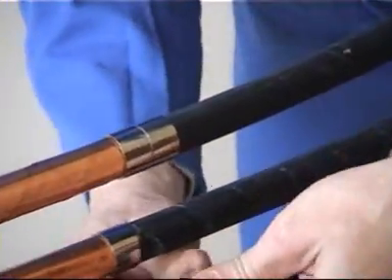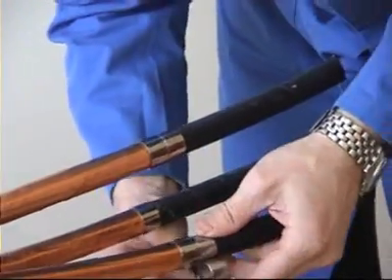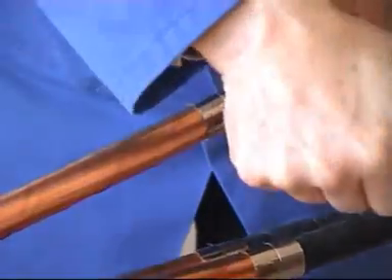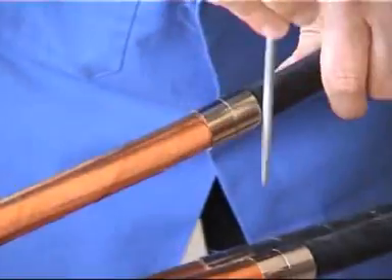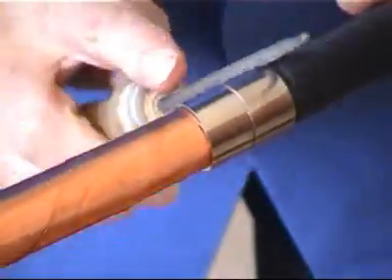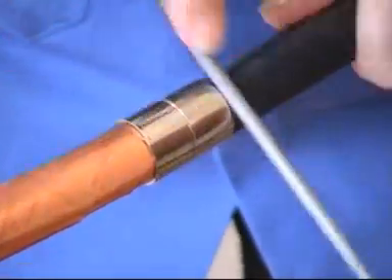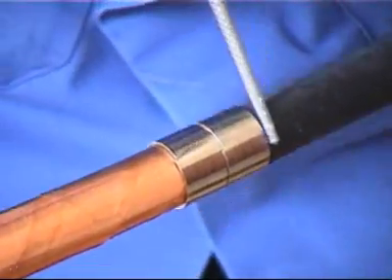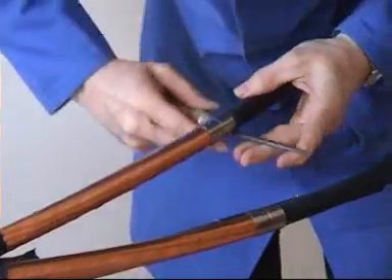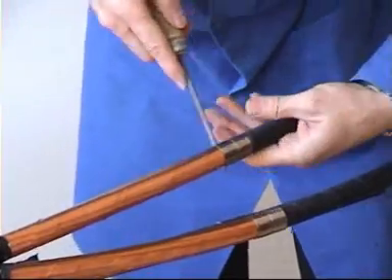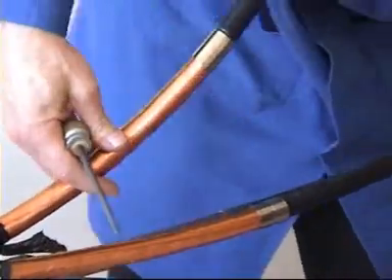We now come to a very important step in the cable preparation on XLP cable. That's the removal of the semi-conductive screen. If done badly, there will be very high discharge levels at the screen cut, and likely termination or joint failure. Use a suitable tool for this, or as shown here, a round rat tail file. Filing against the edge of a roll spring will help you achieve a good even cut.